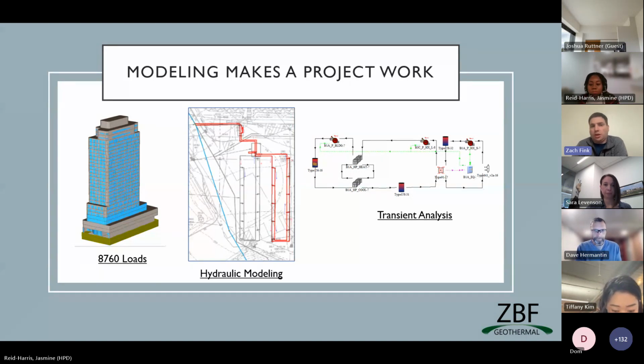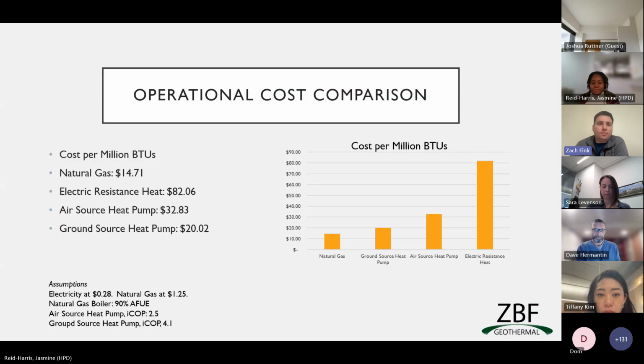Then there's hydraulic modeling to make sure the piping system is robust and we're not going to create any problems - we never want to leak below a building. Most of New York City's boreholes are below the buildings. We also run a transient analysis to see how all the segments of pipe work and how the fluid flows through that. Next slide, please.